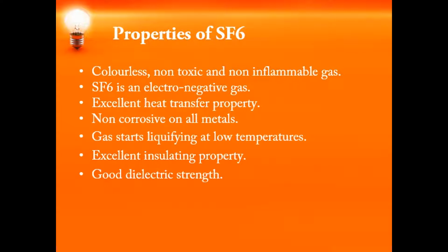What happens is, when a free electron is moving and collides with a neutral gas molecule, the electron is absorbed by this neutral gas molecule and a negative ion is formed. This negative ion is so heavy that it cannot move further, and it cannot ionize more particles. So the arc will be quenched, and the area between the contacts will regain its dielectric property. So SF6 is better compared to oil as well as air circuit breakers.